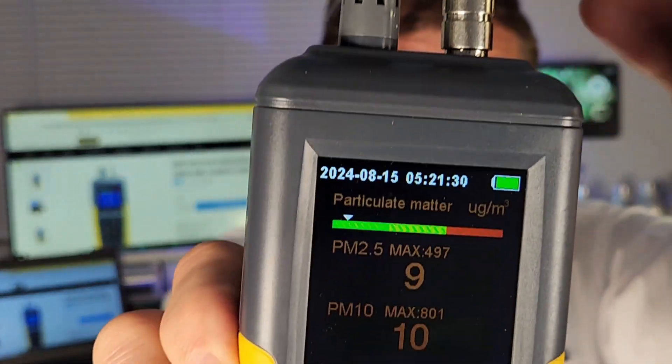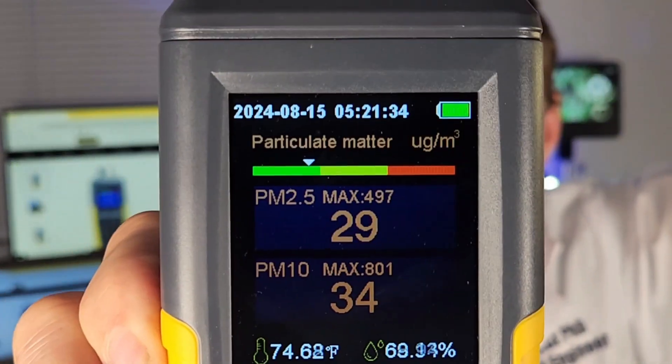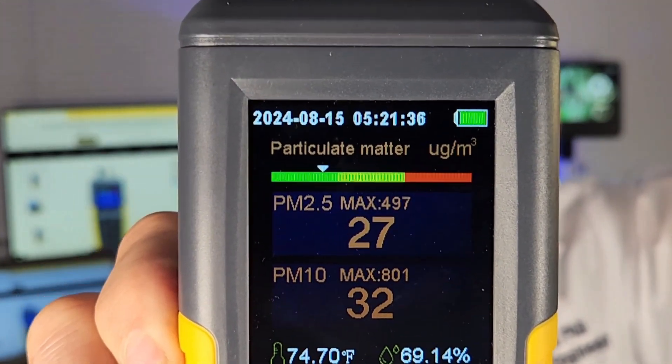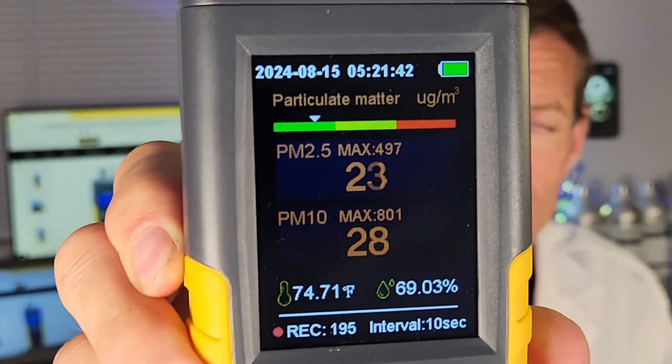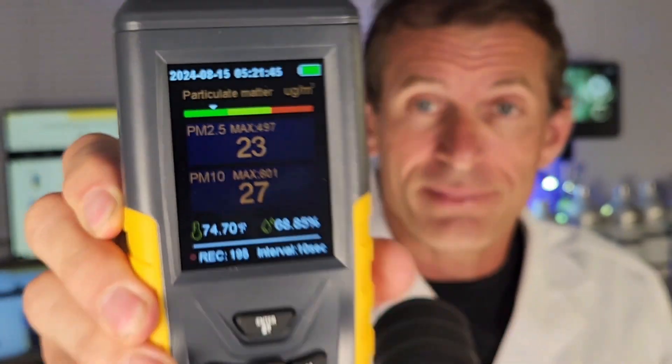It counts all the suspended smoke particles in the air — that is called particulate matter. I have a smoke generator here that I personally use for investigations, and we can generate some smoke. Bringing the unit close to it, you can see the numbers going up as it analyzes the air. Then, as the smoke dissipates, the numbers go down. So you get an understanding on a relative basis — from fresh air to polluted smoke air — how the analyzer responds.